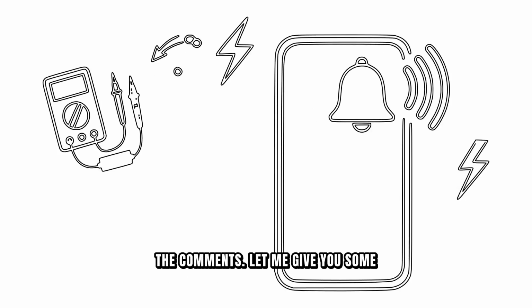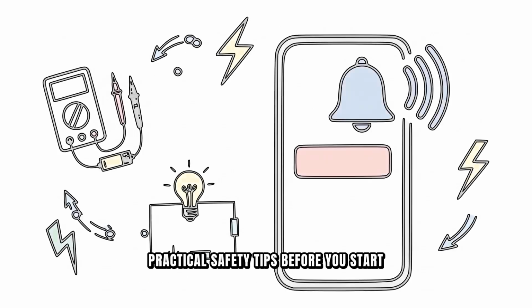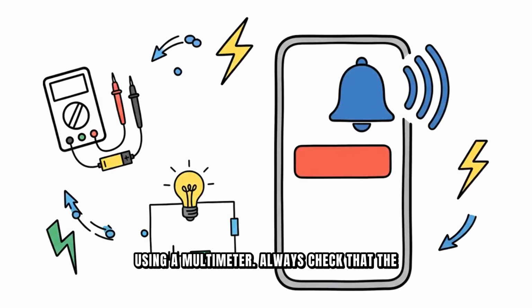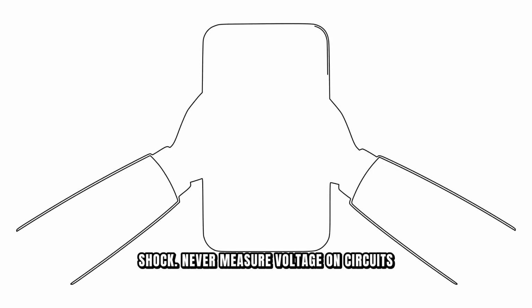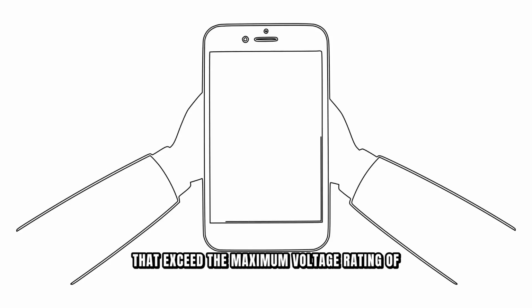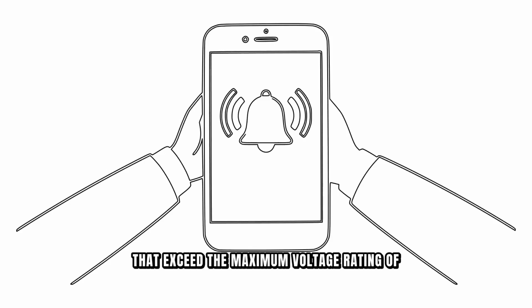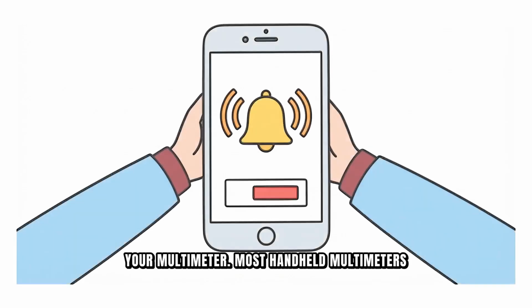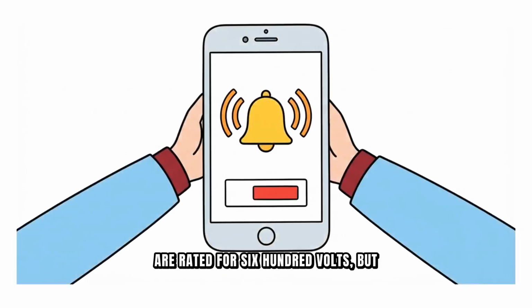Let me give you some practical safety tips before you start using a multimeter. Always check that the probes are in good condition. Cracked or damaged insulation can cause electrical shock. Never measure voltage on circuits that exceed the maximum voltage rating of your multimeter. Most handheld multimeters are rated for 600 volts, but some measure higher.